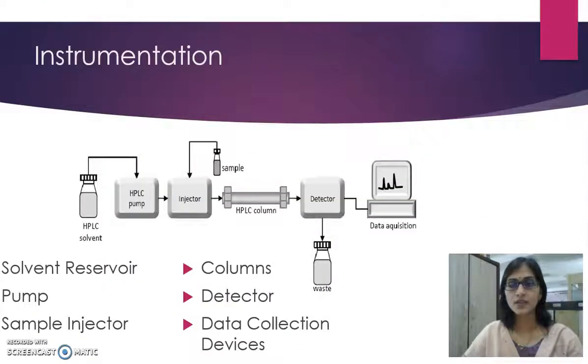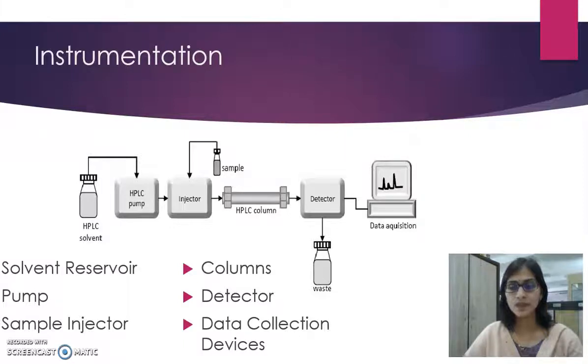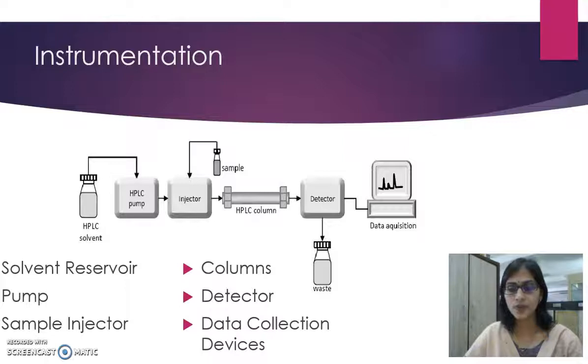Now we will see the instrumentation of HPLC. It consists of a solvent reservoir, pump, injector, column, detector and a device for data acquisition. The solvent reservoir is used to contain the mobile phase, and the pump is used to force a liquid through the liquid chromatograph at a specific flow rate, expressed in milliliters per minute. Normal flow rates in HPLC are in the 1 to 2 ml per minute range. Typical pumps can reach pressures in the range of 6,000 to 9,000 PSI.